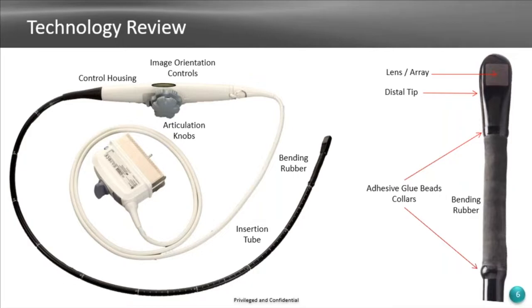This is where the magic happens with this probe. These arrays are extraordinarily fragile, so just something like that will damage that array. All these arrays are already damaged, so I can do whatever I want with these probes, but when people are cleaning them or rinsing them in the sink, they'll be banging them around the sink trying to get excess liquid off. That will destroy that array. Just something as small as minor impact, and we have our distal tip, which is the entire transducer tip.